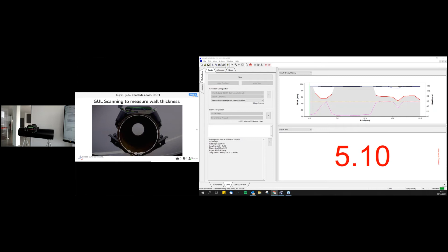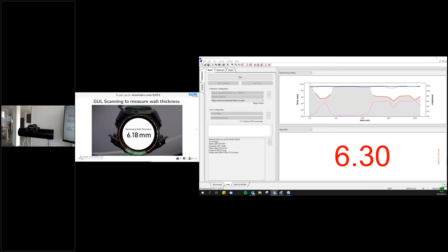So we don't rely on looking at the change in amplitude between a good and bad signal. We focus on calculating the remaining wall thickness for each location. A good analogy to describe this frequency-based analysis is to consider a cup filled with water. If you fill a cup right up to the brim and you start rubbing the edge to generate a resonant sound, you will hear a relatively low pitched sound, which is analogous to a good pipe.